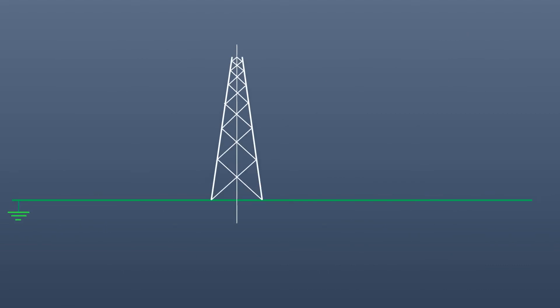At this picture, a structure of a substation holding power line with accessories. Suppose an earth fault EF occurs between the line and the structure body. Fault current IS flows through the structure to earth, and subsequently voltage appears at the substation structure as well as at the surface of the substation near the fault structure.